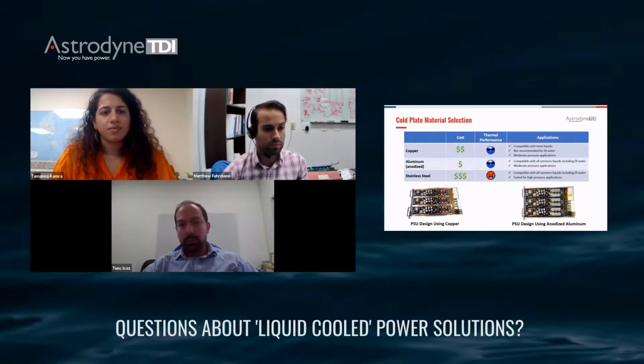So copper is compatible with most fluids, but it's not recommended for deionized water applications. There might be folks in the audience who use deionized water in their current systems, or are considering designing it. Copper is known to have long-term corrosion issues with deionized water. Bare aluminum has known corrosion issues with fresh water or water applications in general.